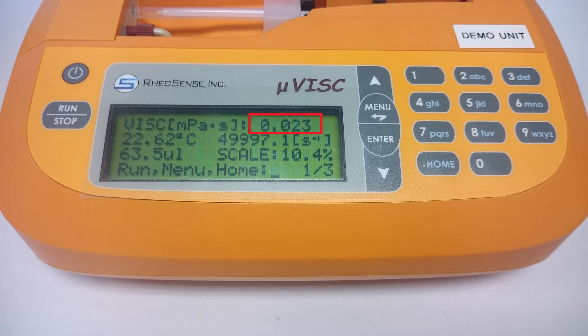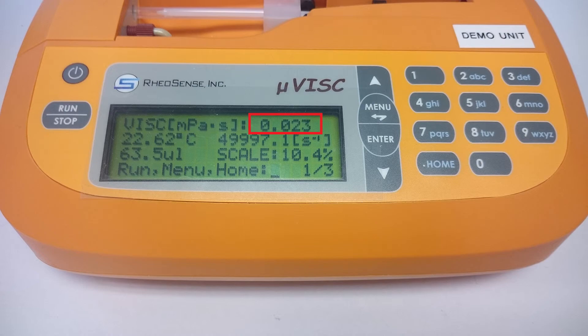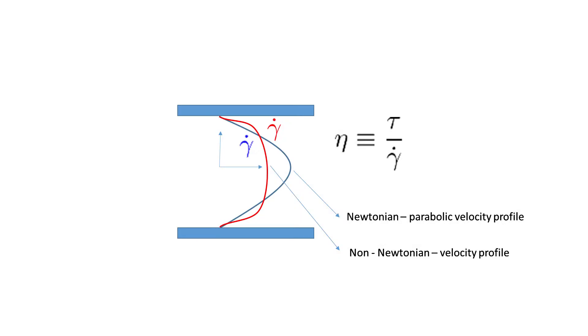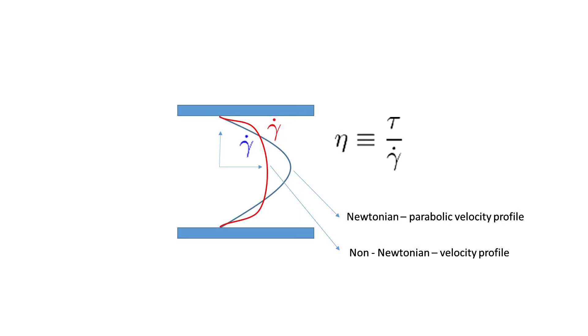For a non-Newtonian sample, this viscosity value is the apparent viscosity. It will be consistent for this chip, but it may not match up with values obtained from rheometers. This is due to the flow profile exhibited in tubes by non-Newtonian fluids.